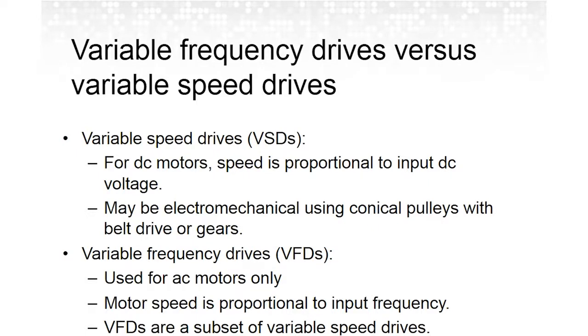We mentioned variable frequency drives and variable speed drives. Variable speed drives are the general category. For DC motors, you can have a variable speed drive where the speed is proportional to the DC input voltage. And a variable speed drive can be electromechanical, using cone pulleys or belt drives or gears. Variable frequency drives are a special case of variable speed drives that are used for AC motors only. The motor speed is proportional to input frequency.